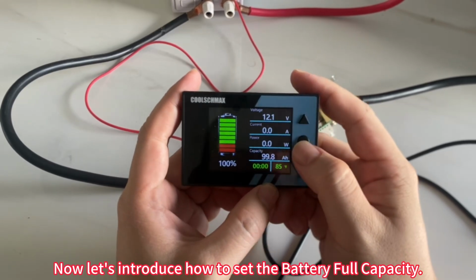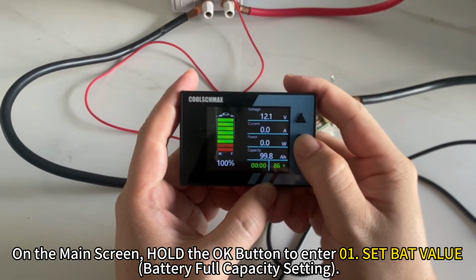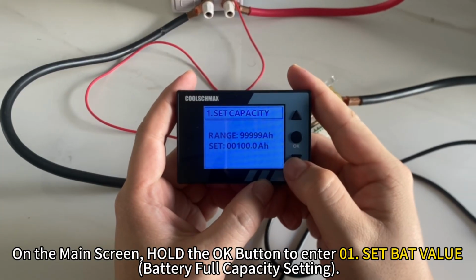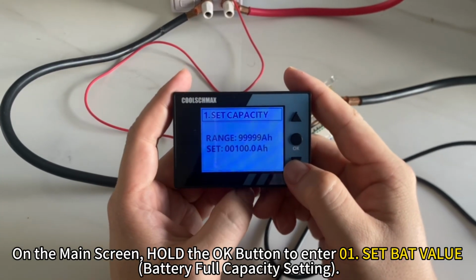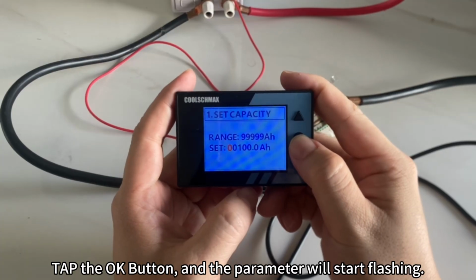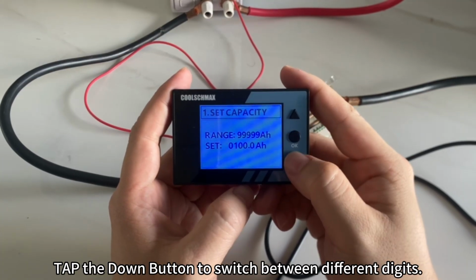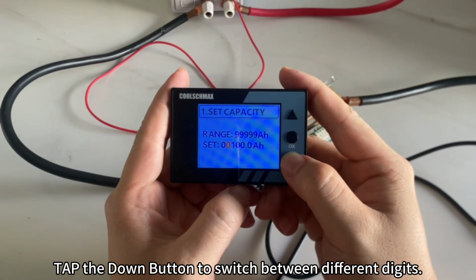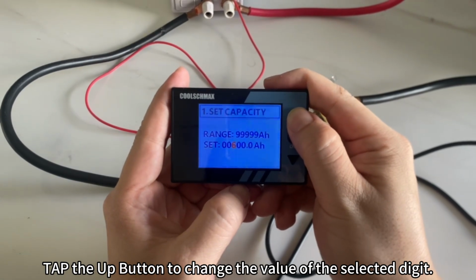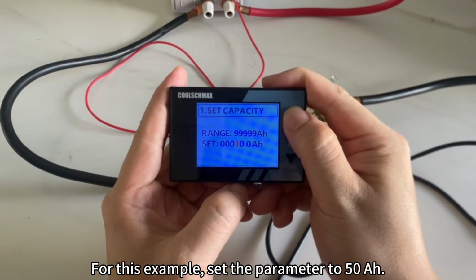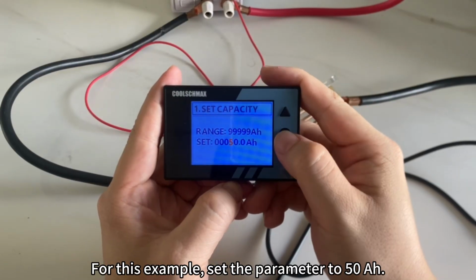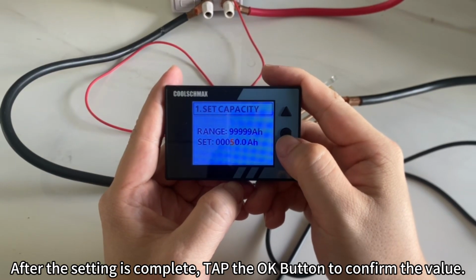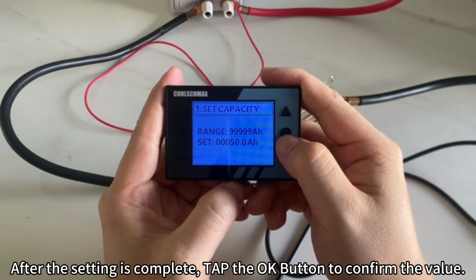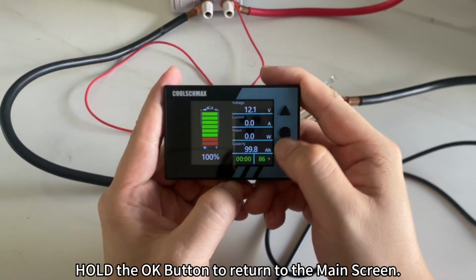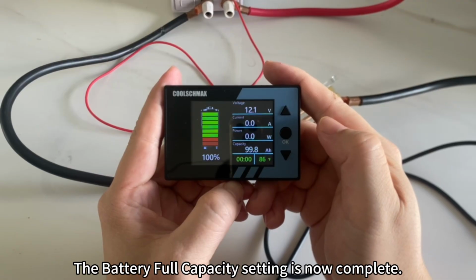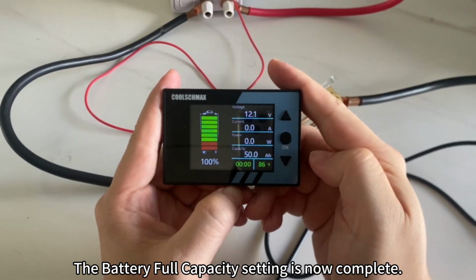Now let's introduce how to set the battery full capacity. On the main screen, hold the OK button to enter 01. Set bat value. Tap the OK button, and the parameter will start flashing. Tap the down button to switch between different digits. Tap the up button to change the value of the selected digit. For this example, set the parameter to 50 Ah. After the setting is complete, tap the OK button to confirm the value. Hold the OK button to return to the main screen. The battery full capacity setting is now complete.